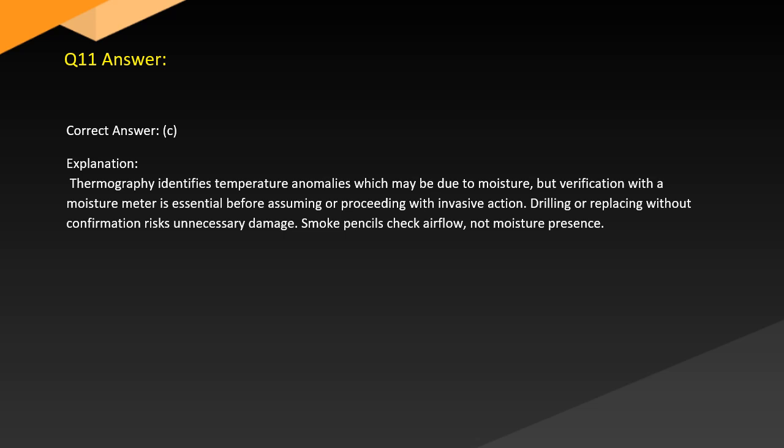Answer. Correct answer: C. Explanation. Thermography identifies temperature anomalies which may be due to moisture, but verification with a moisture meter is essential before assuming or proceeding with invasive action. Drilling or replacing without confirmation risks unnecessary damage. Smoke pencils check airflow, not moisture presence.